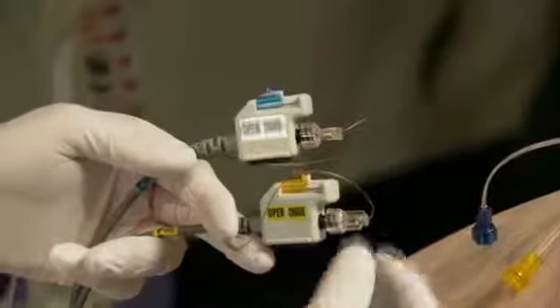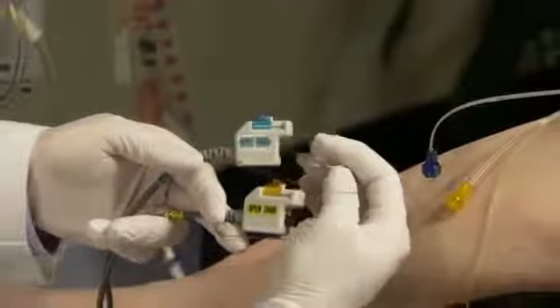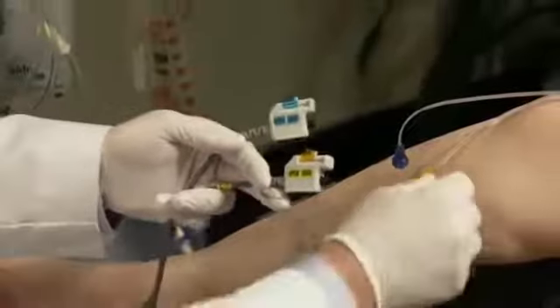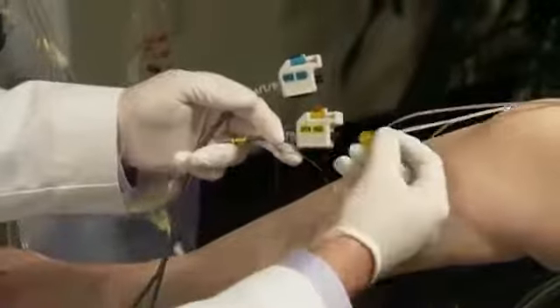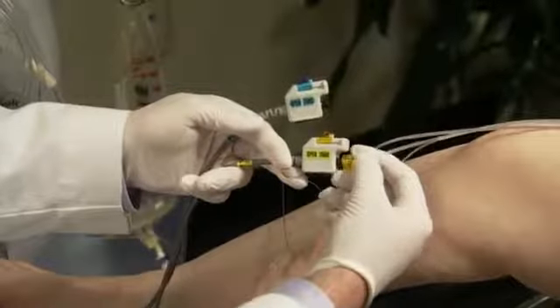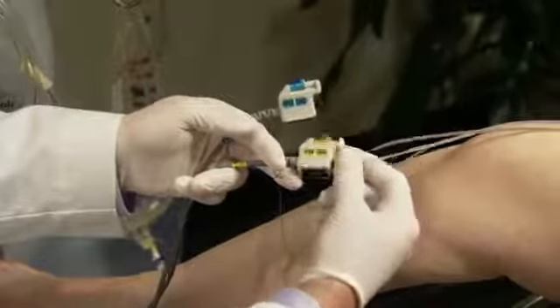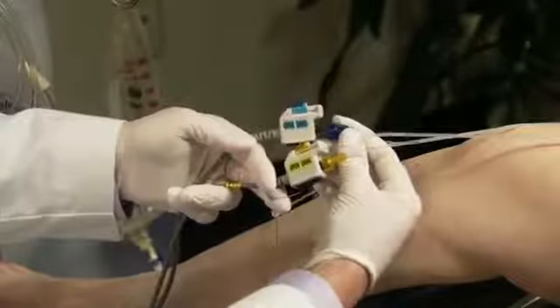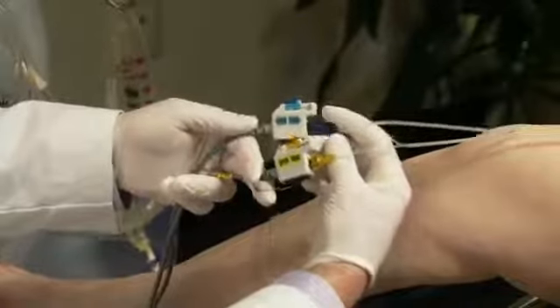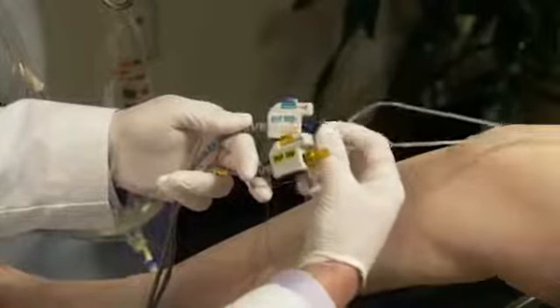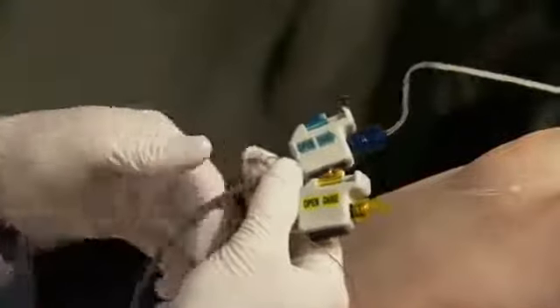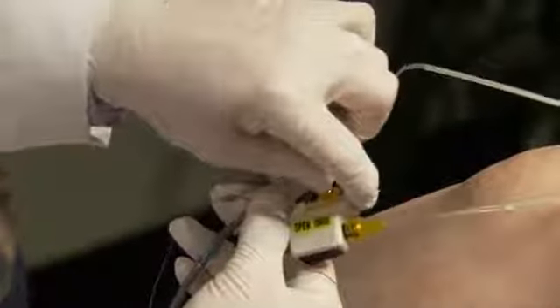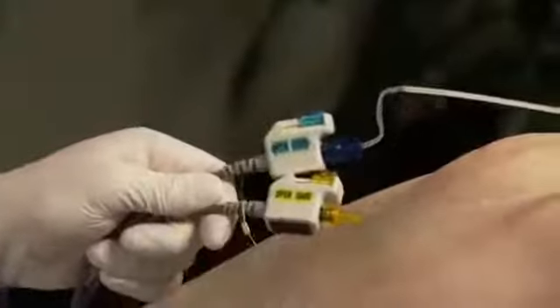Once the catheters and EMG leads are placed on the patient, remove the protective caps from the TDOC transducer cables and ensure they are in the open position. Then attach the catheters to the color-coded cables. P vesicle is yellow, P detrusor is blue, and if measuring UPP, P urethral is green. Next, press 0 all. Lastly, charge the catheters by moving the transducer from the open to charge position.